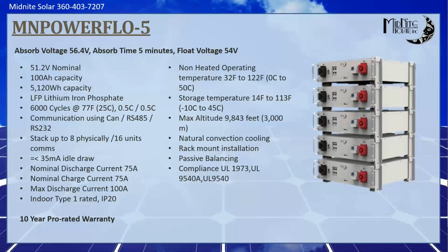But as an example, I worked with a customer the other day on an 18 stack, and the last 2 just don't communicate with the inverter, but you don't really need them to at that point because the amp hour capacity of the battery is such that the inverter is not going to throttle because of those 2 batteries.